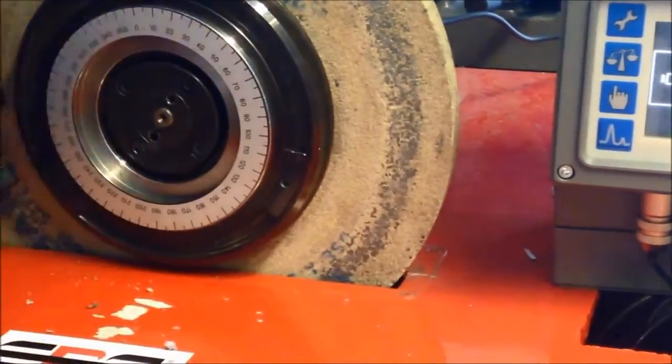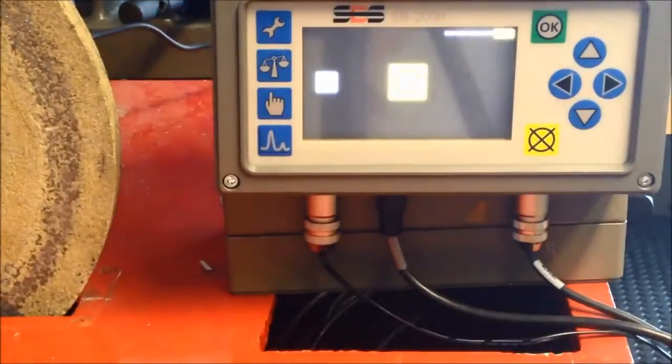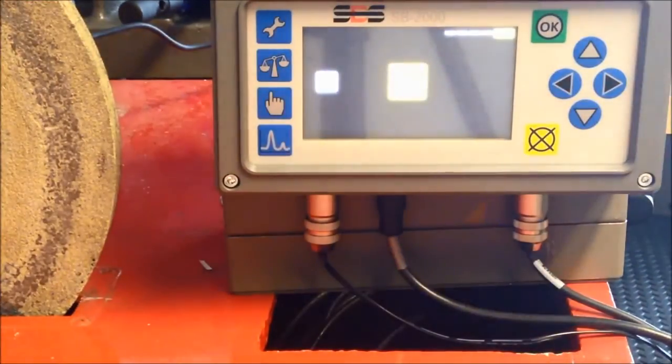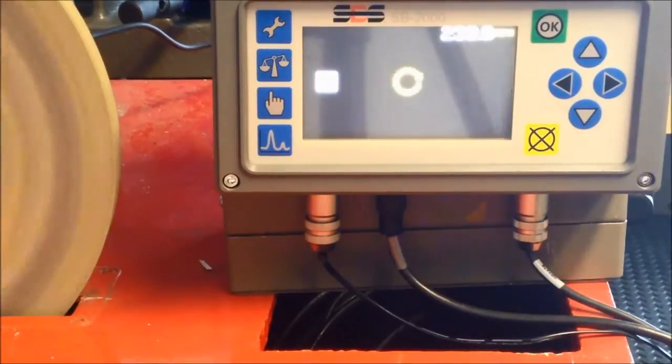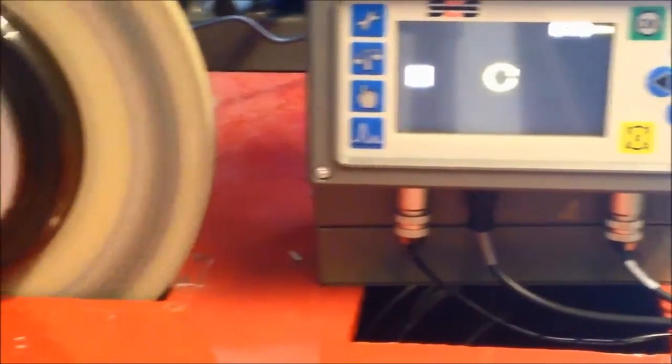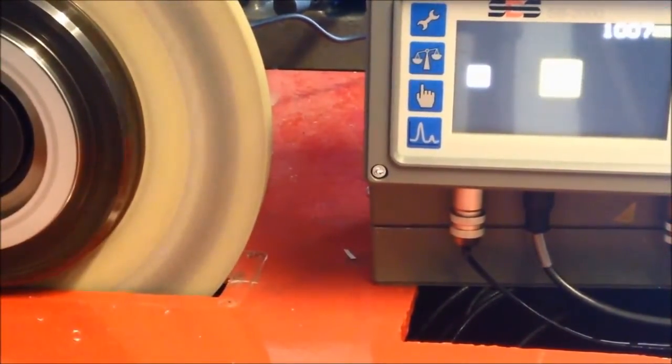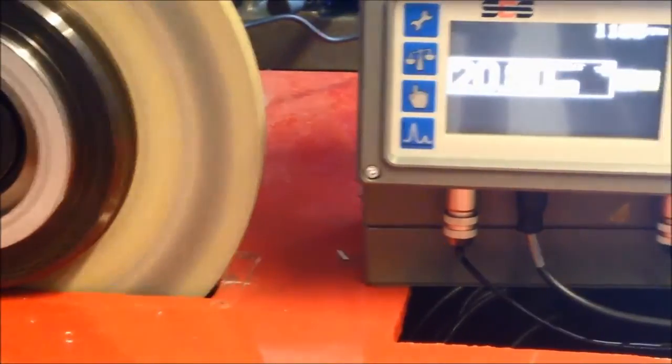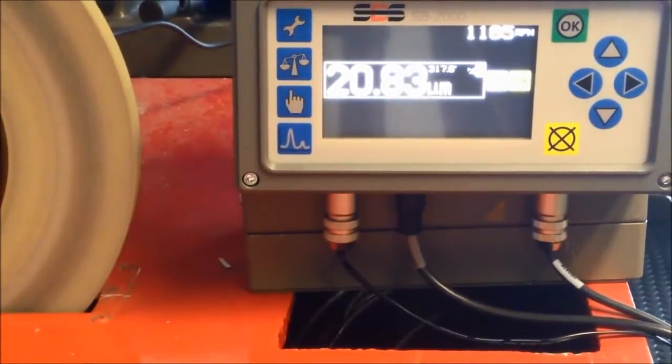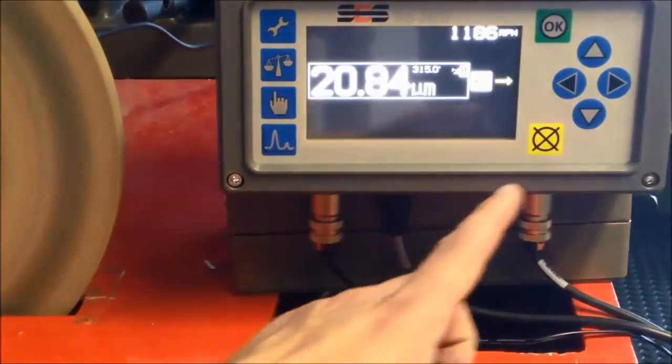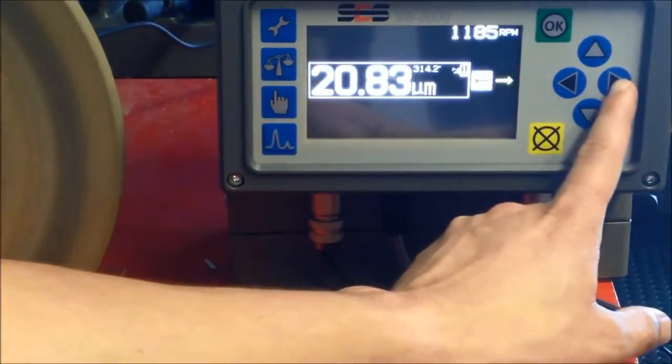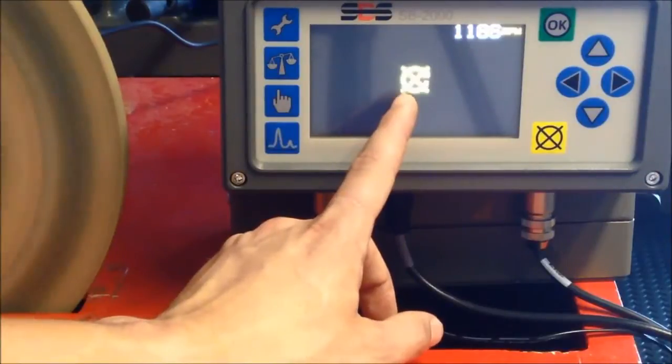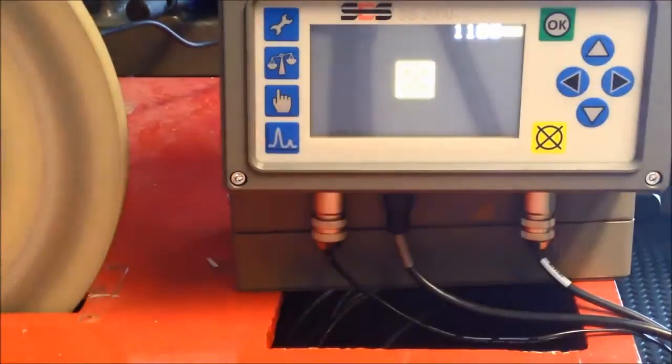When you are happy the weights are at the correct angles, press next and start the spindle. As the weights are in the null position, we can see that the grinding wheel in its raw state is inducing 20 microns of vibration into the spindle. Press next when the readings stabilize and stop the spindle.